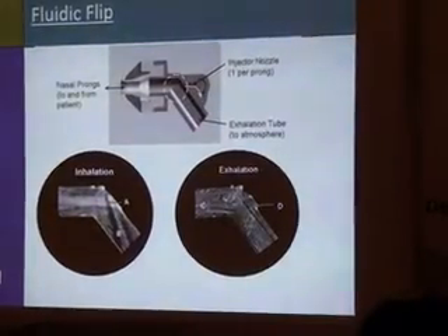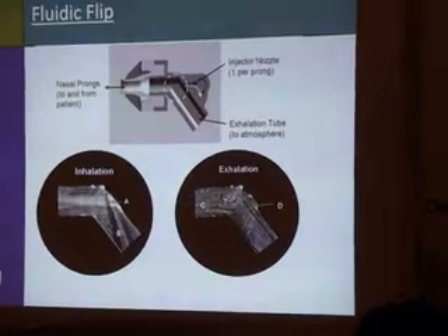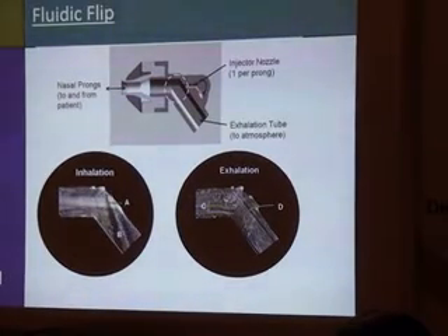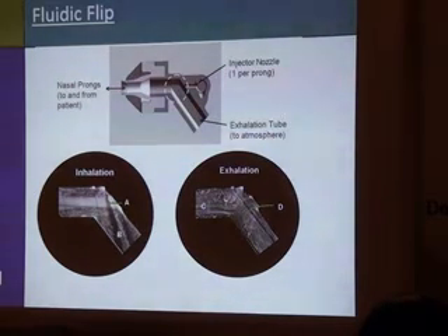There are 2 different types. There are 2 different companies that had the same type of system. They merged, so now depending on which headgear you buy, it's different. The one is the Fluidic Flip, and this is the older headgear. So the magic really happens with this machine in the flow generator that's on the face. So it's all right here. There's a system here where you have your injector nozzle with all of your flow going through, and then you have this tubing here that is a dump out, or an expiratory tube that goes out to atmosphere. That provides the expiratory dump.